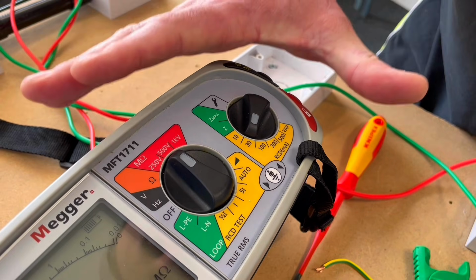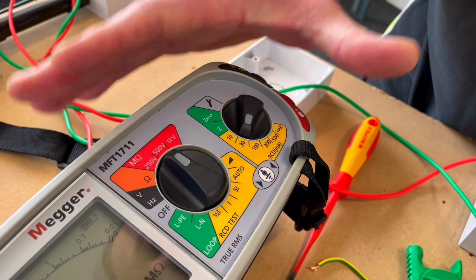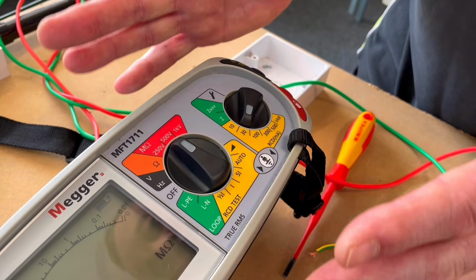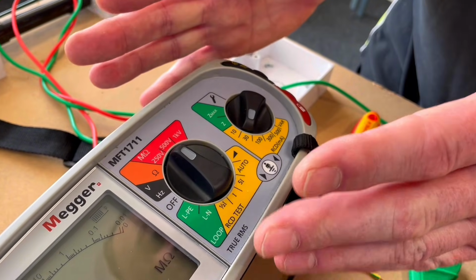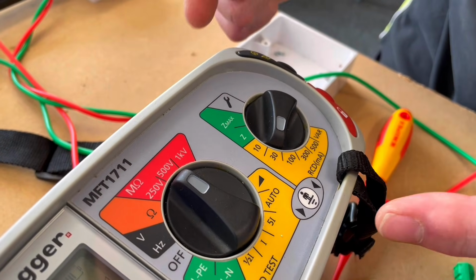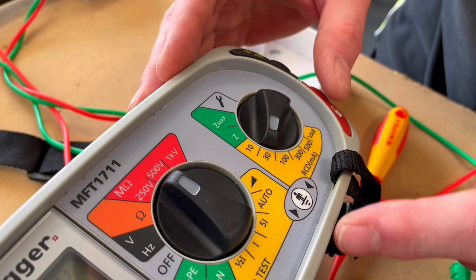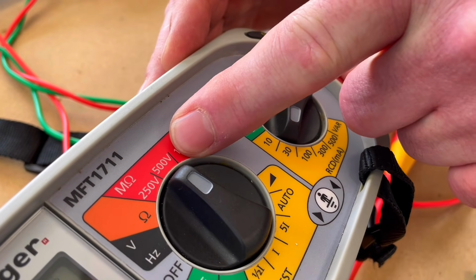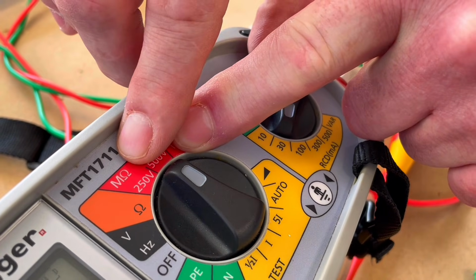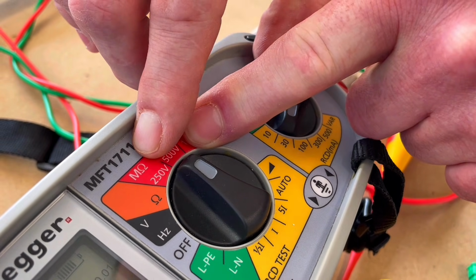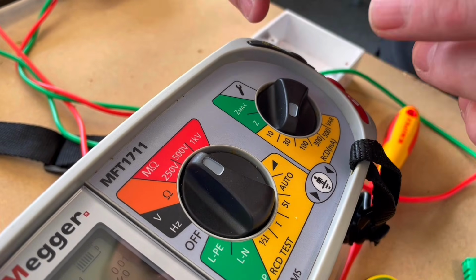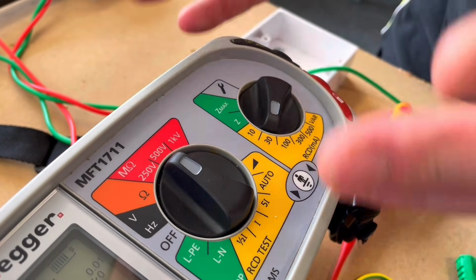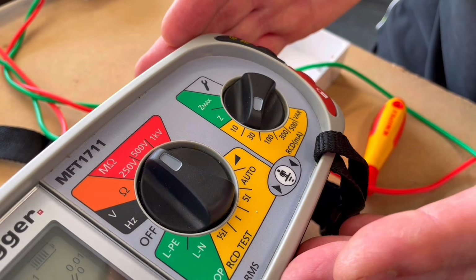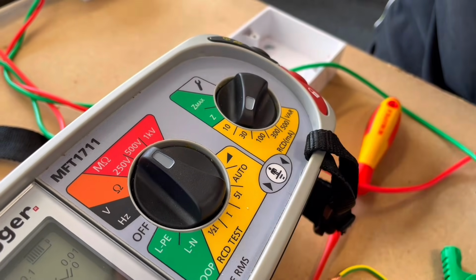I expect the insulation resistance reading to be very, very high. I've done a separate video explaining about insulation resistance and length of conductors, and again I'll leave a link for that video if you haven't already seen it. So for this test, it's 500 volts DC. We're in the megohm scale, and we're going to be expecting a reading very, very high, possibly an infinity reading, or one greater than the machine can read, as we measure its insulation resistance.